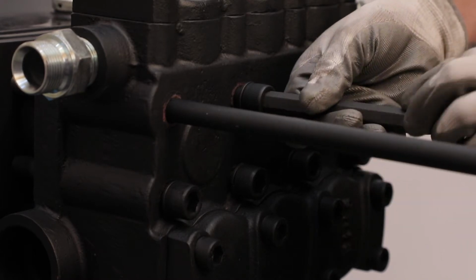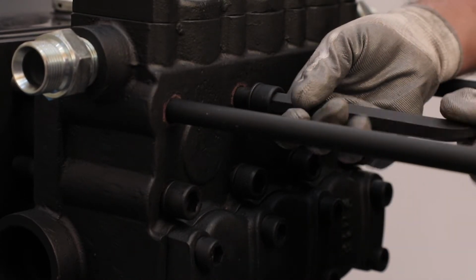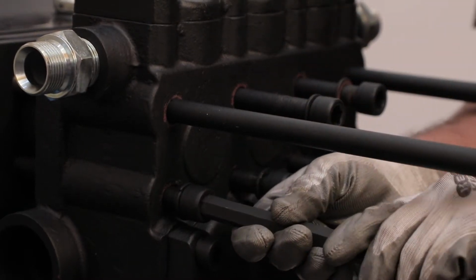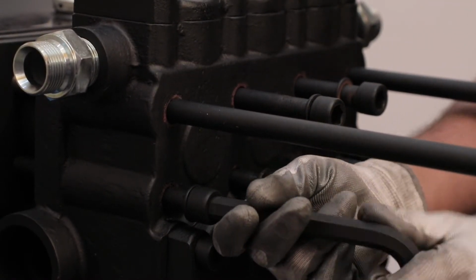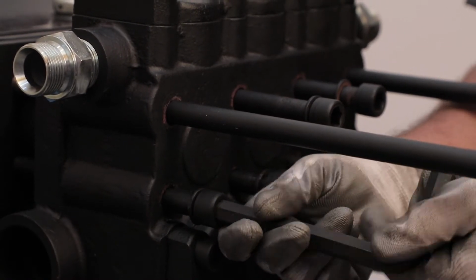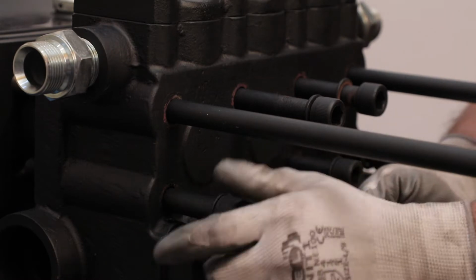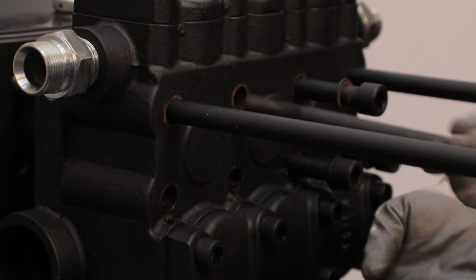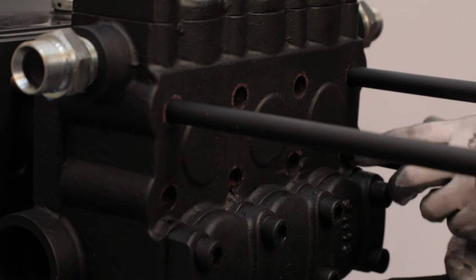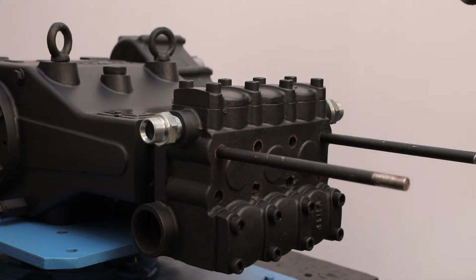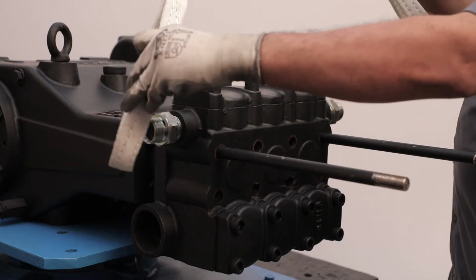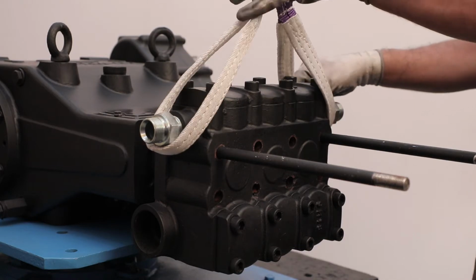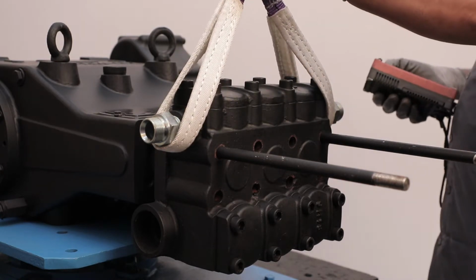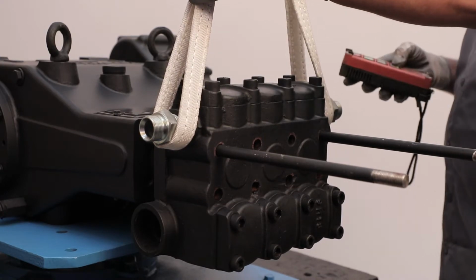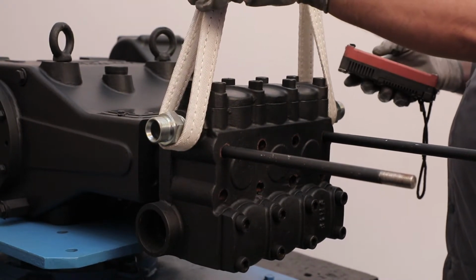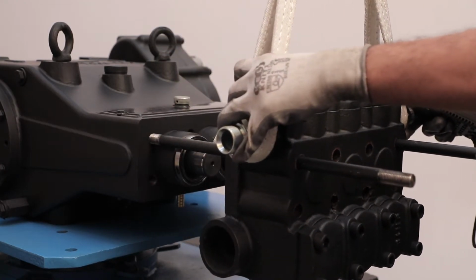Make sure the adapter should be installed on both sides of the pump. Take lifting belt and hold it with an adapter from both sides. With help of a lifting belt and crane, separate the pump head from crankcase and place the pump head on a clear and safe surface.